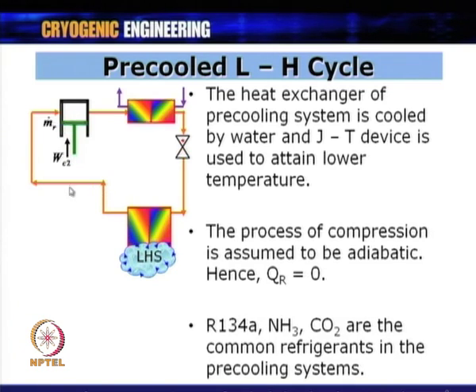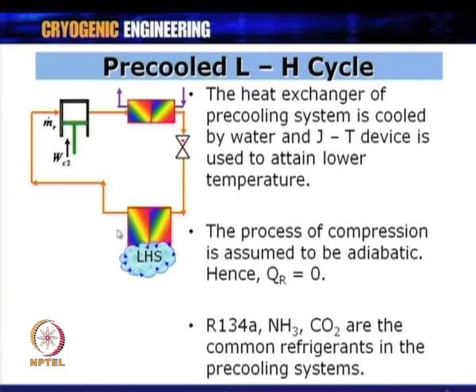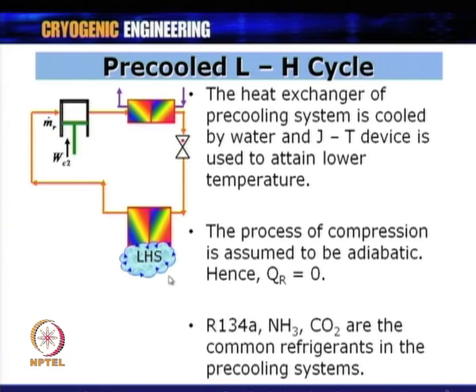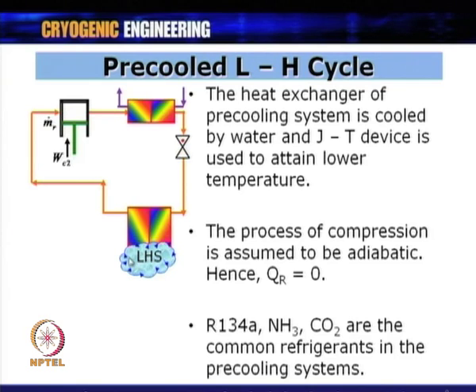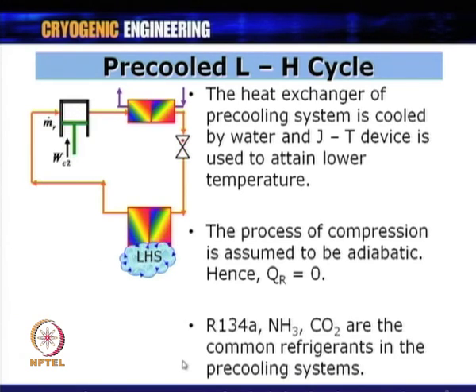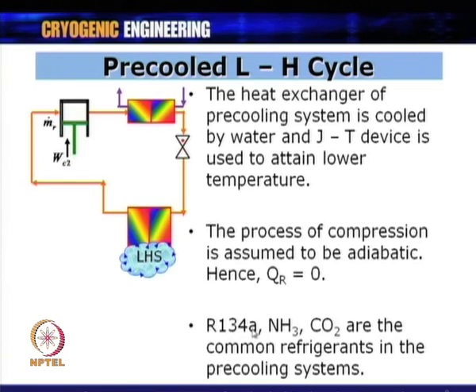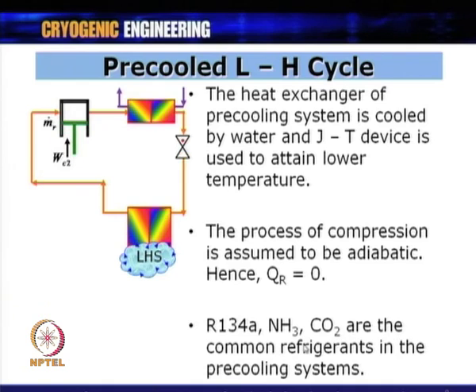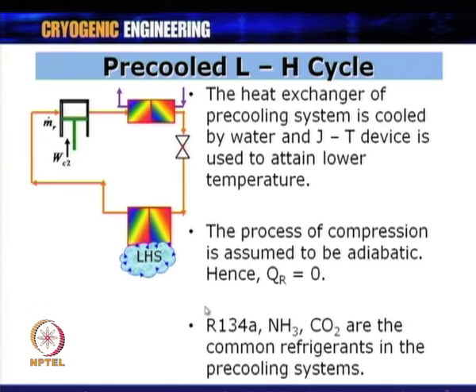The pre-coolants are refrigerants chosen based on the desired pre-cooling temperature. Common refrigerants used in pre-cooling systems include R134A, ammonia (NH3), CO2, and others. The choice of refrigerant determines the compressor, condenser, expander type, and also the achievable pre-cooling temperature.